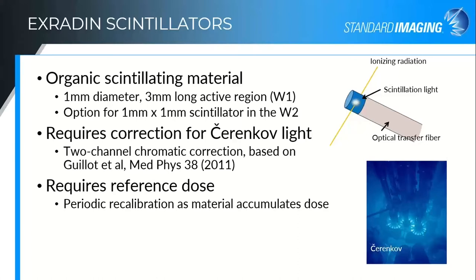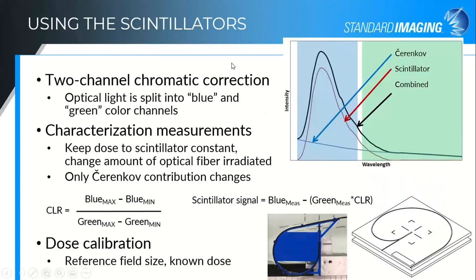You do need to recalibrate it periodically as it accumulates dose. We get about a 2% decrease in signal for every thousand gray that it receives. The two-channel chromatic correction splits the optical signal into two sections of the spectrum — we call one the blue region and one the green. The blue region is primarily the scintillation signal along with some contaminant Cherenkov, and the green is primarily Cherenkov, although a little bit of the scintillation signal bleeds over into that as well.